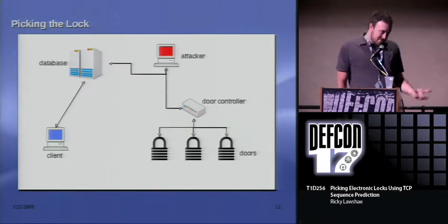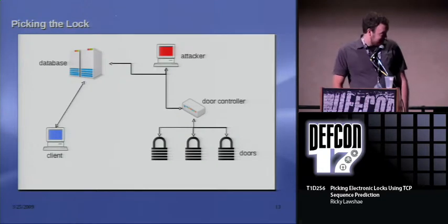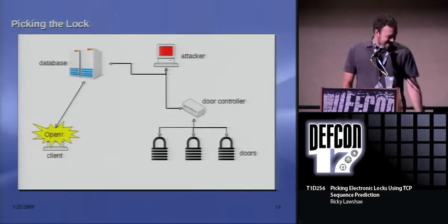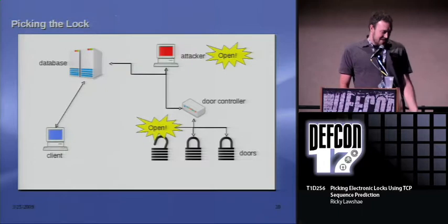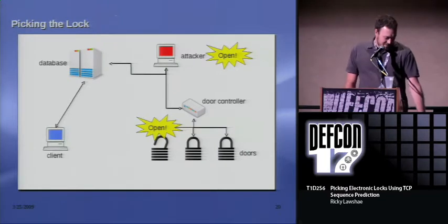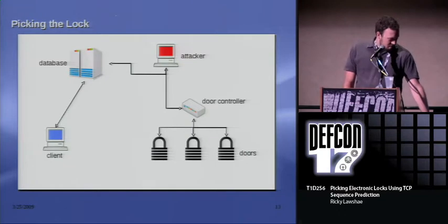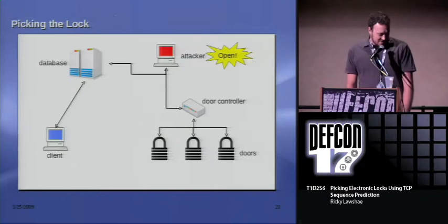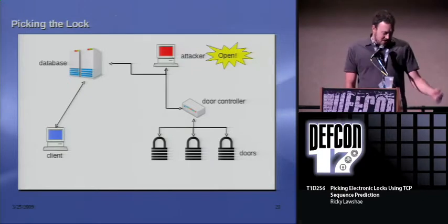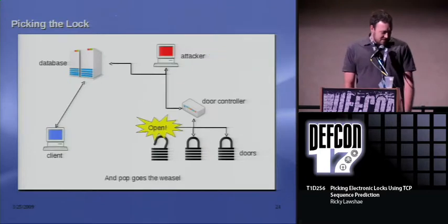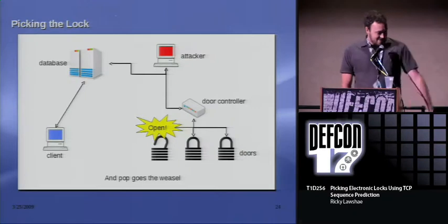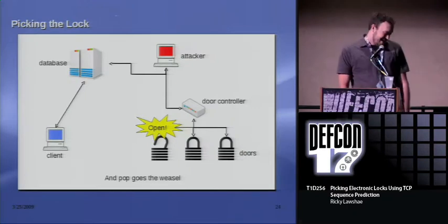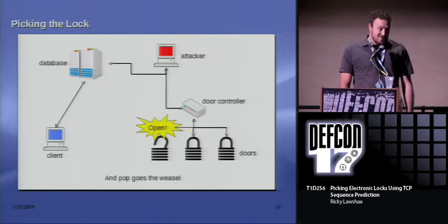Now, what happens in this scenario — and you can tell he's the bad guy because he's red. The client says 'open the door' and now the attacker has a copy of that command. Some time goes by and he says 'I want to open the door' — and pop goes the weasel. The door controller interprets it just like any other command. You'll notice that nothing happened on the database at all, so there's no log of the command. No alarms are tripped because the door controller saw it as a valid open.